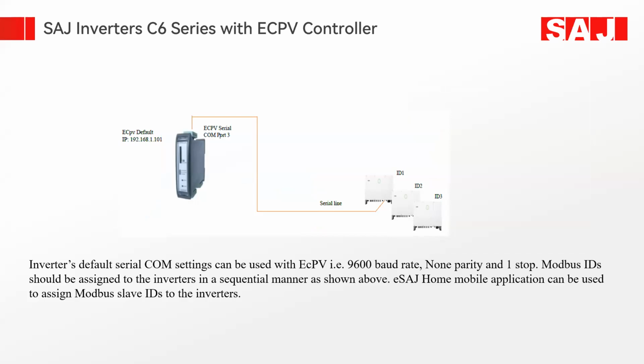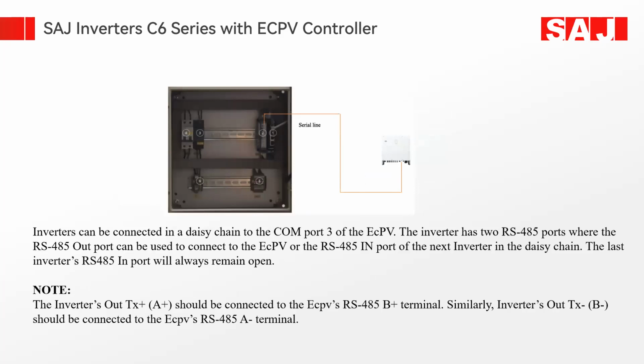The ECPV default IP address is 192.168.1.101. It's for the third-party diesel genset controller companies. Inverters can be connected in a daisy chain to COM port 3 of the ECPV. The inverter has 2 RS485 ports, where the RS485 output can be used to connect to the ECPV or the RS485 in port of the next inverter in the daisy chain. The last inverter's RS485 in port will always remain open.